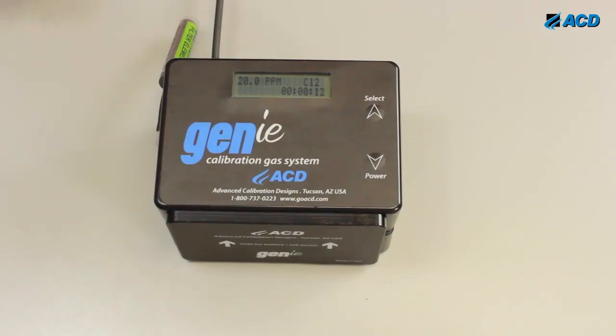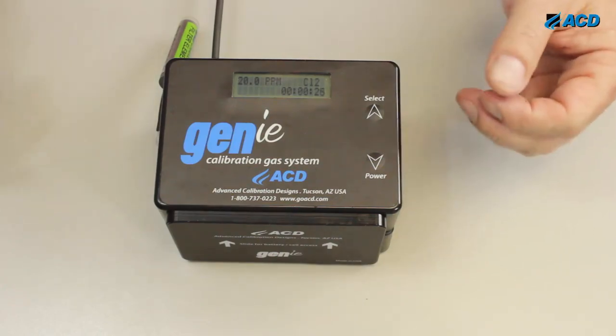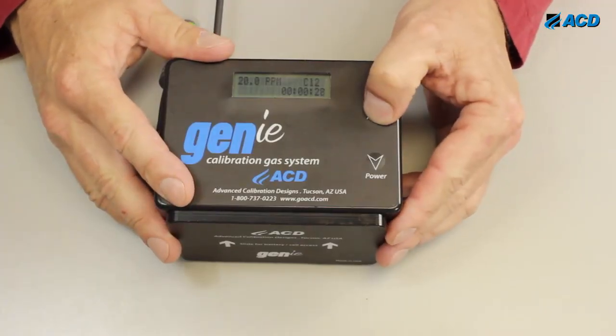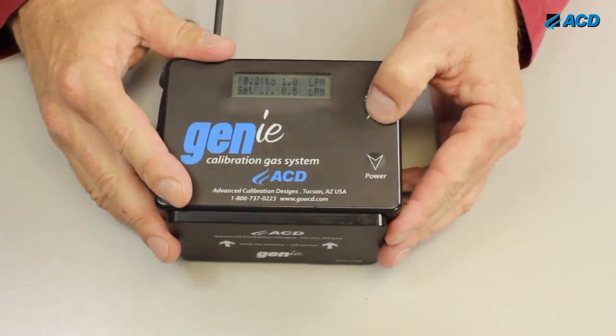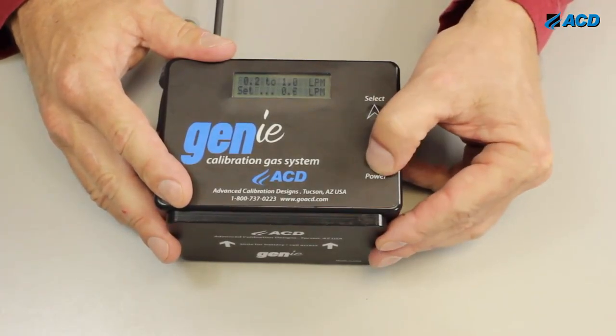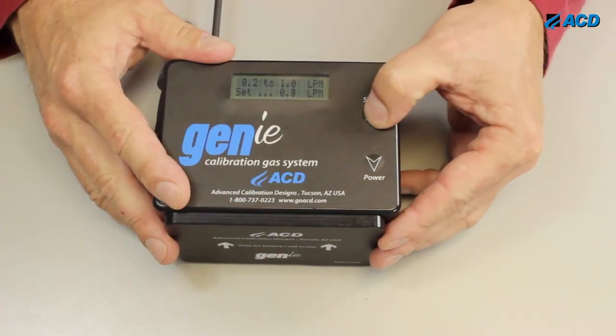So we run around our facility, we calibrate, we have one brand that is all 20 parts per million. We go calibrate all those. We're all done. Now we've got another brand of sensors that wants 5 parts per million, let's say. So if I want to change the output, I hit the select button. The flow, it says flow select to change, so that shows me between 0.2 and 1.